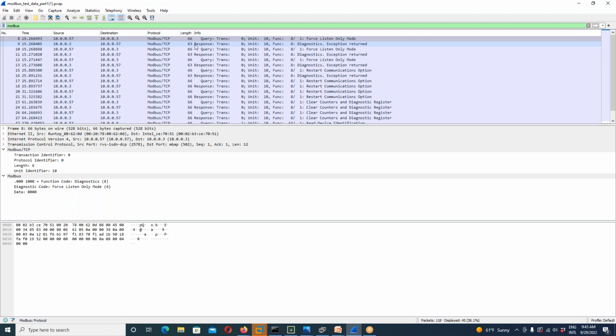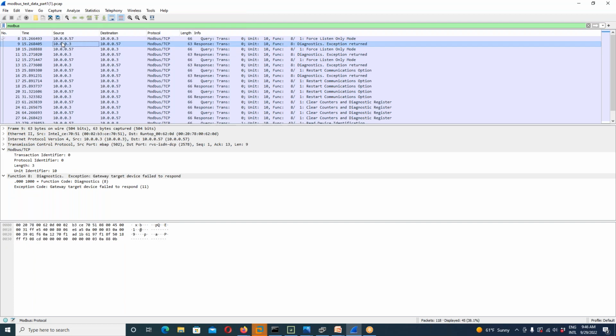Let's take a look at some of these others. Now here's the response from that same PLC - let's see how it responds. It comes back with unit identifier 10, function code 8, diagnostics, gateway target device failed to respond. So it's throwing an exception code - the gateway target device failed to respond. Here's exception diagnostic code 8.